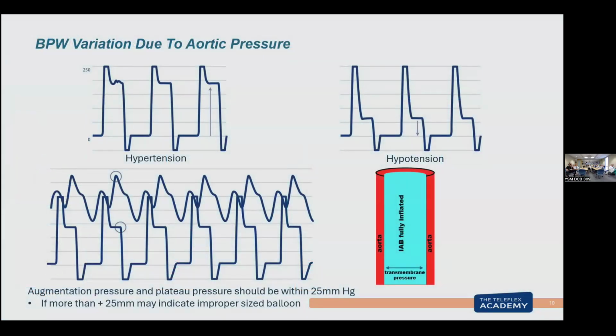Now, the other thing we can tell is what's happening inside of the aorta against that balloon, because this is calibrated. So if I've got somebody who's vasoconstricted or hypertensive, the pump's going to have to use more pressure to push that volume to the balloon. So the plateau elevates because it says, I'm going to get it all in there, but I've got something pushing against me, so I'm going to have to raise that pressure. And if he's vasodilated, hypotensive, it doesn't take very much pressure to push that 40 in, so the plateau will be lower.